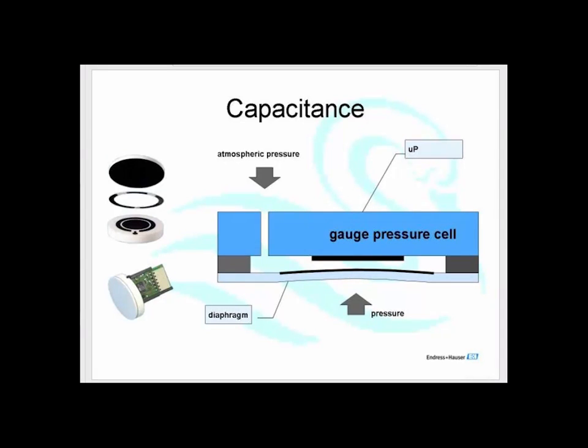The fact is that the ceramic pressure cell has completely revolutionized pressure measurement. Nowadays we use a capacitive ceramic pressure cell unless there's an incredibly good reason not to, something like it being over 400 degrees C or over roughly 2000 kPa. You must have extremely high pressure or extremely high temperature; otherwise, you use a ceramic pressure cell.